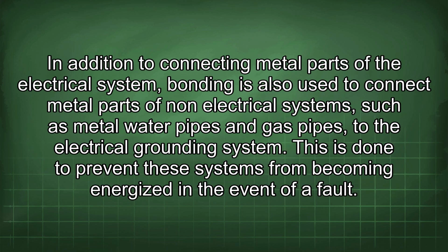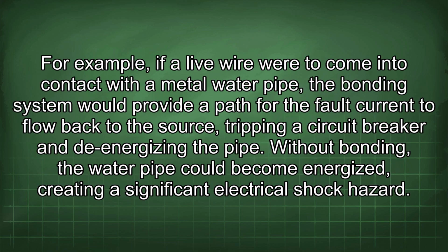In addition to connecting metal parts of the electrical system, bonding is also used to connect metal parts of non-electrical systems, such as metal water pipes and gas pipes, to the electrical grounding system. This is done to prevent these systems from becoming energized in the event of a fault. For example, if a live wire were to come into contact with a metal water pipe, the bonding system would provide a path for the fault current to flow back to the source, tripping a circuit breaker and de-energizing the pipe. Without bonding, the water pipe could become energized, creating a significant electrical shock hazard.